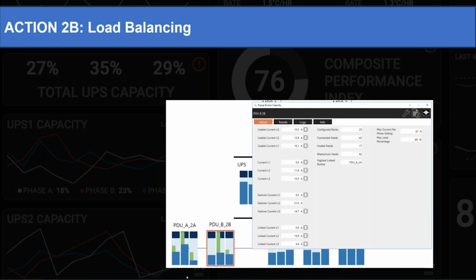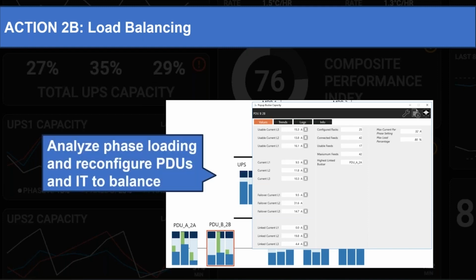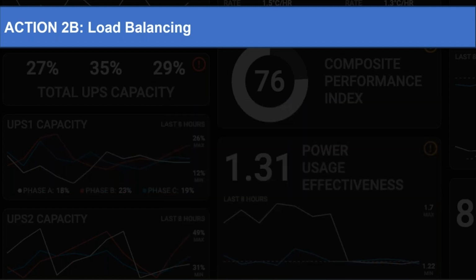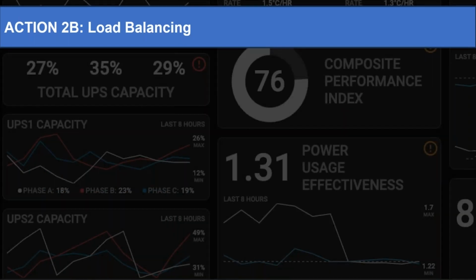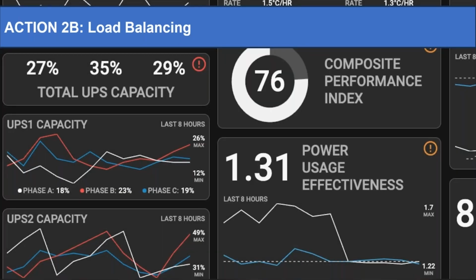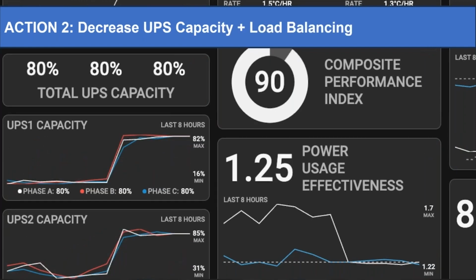And the next step is load balancing. The way we are showing it, the darker blue lines are the actual loads, and you can see an imbalance, and the green ones are the failovers, and that's your redundancy. So in this case, it's not balanced and you have lost your failover redundancy. That's wrong. By balancing, you will save a lot of money, because then the zero currents will disappear, and that means, theoretically, your cable lengths will be cut in half. So your losses will be gone in this situation. So that's the next step, load balancing. Make sure that every feed has the same load. So not those big steps anymore. So that's what I did.